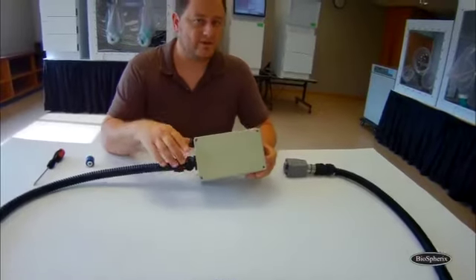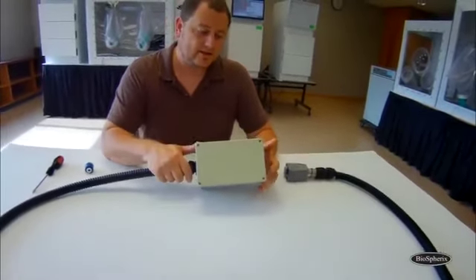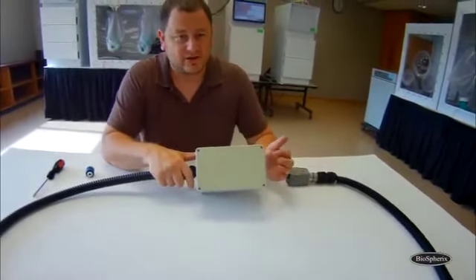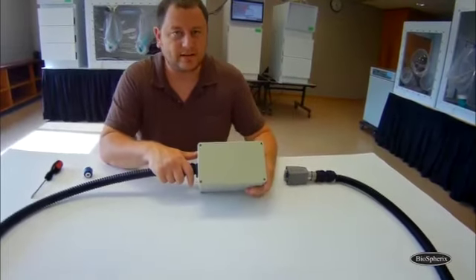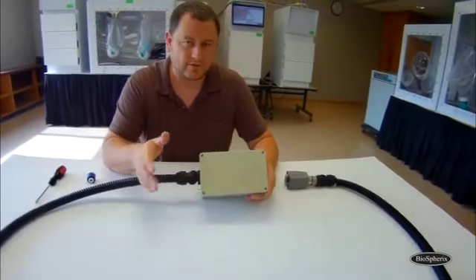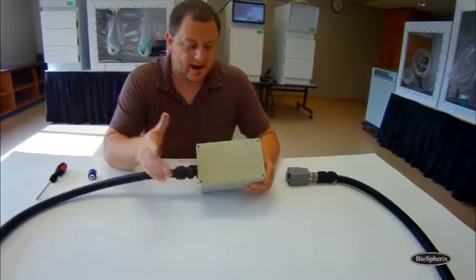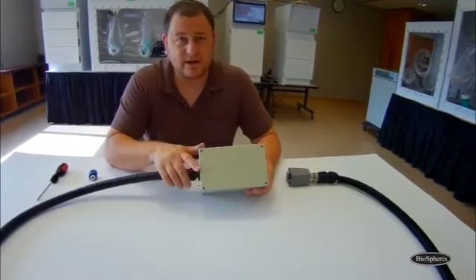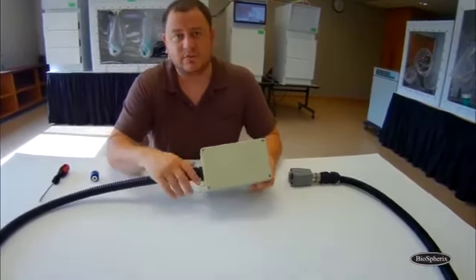It is an electrochemical sensor, so it drifts, and once a month calibration will correct that drift, keep your reading nice and accurate. And about every 2 to 3 years, depending on oxygen exposure, you'll have to replace it.